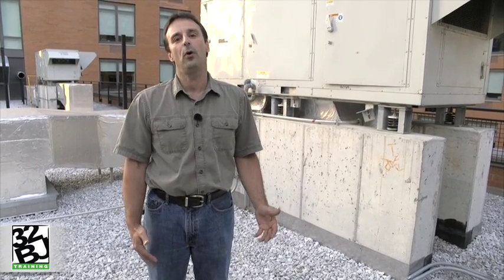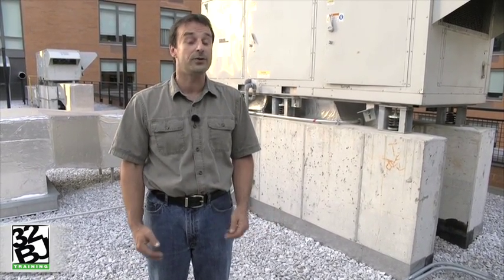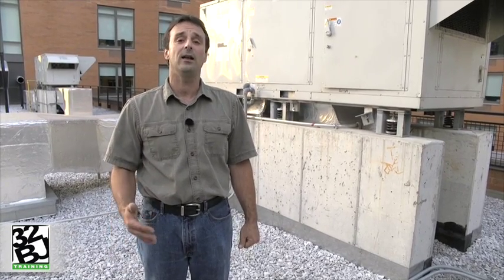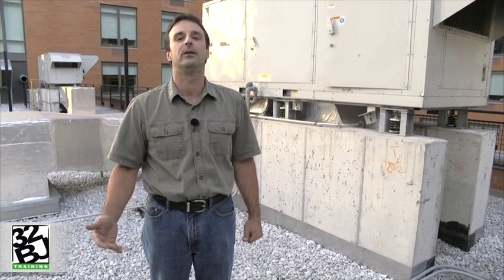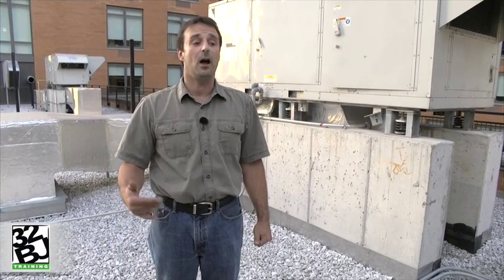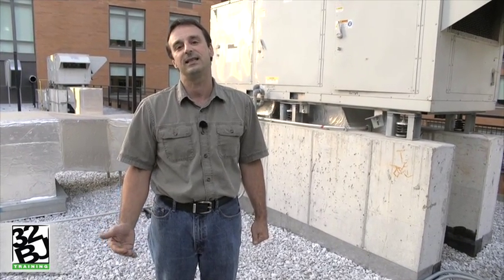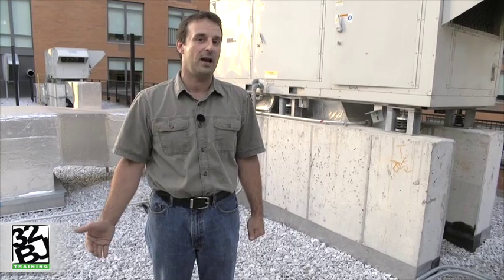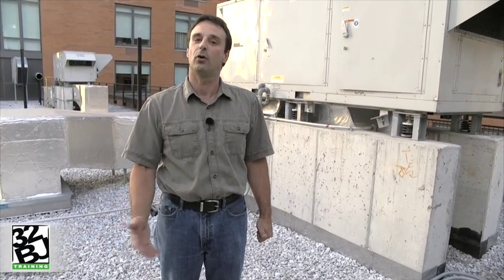Remember, the job of the hallway ventilator, or its controls, is to control a constant discharge air temperature leaving the machine, sending in a constant 67 to 68 degrees all year round in order to provide air for ventilation. This is why you should never find a typical thermostat in one of your common corridors controlling your hallway ventilator. It's being controlled by the equipment inside this machine.